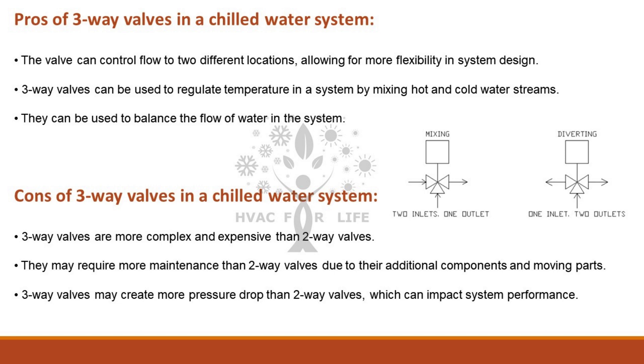Cons of three-way valves in a chilled water system: three-way valves are more complex and expensive than two-way valves. They may require more maintenance due to their additional components and moving parts. Three-way valves may also create more pressure drop than two-way valves, which can impact system performance.